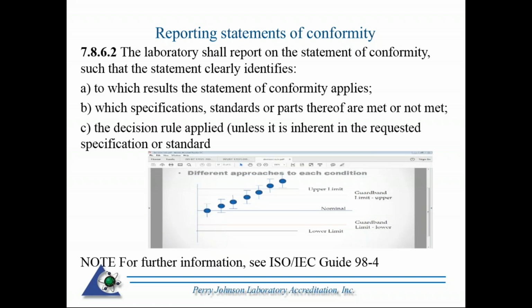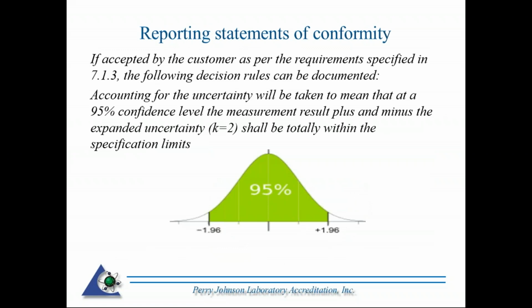7.8.6.2: the laboratory shall report on the statement of conformity such that the statement clearly identifies to which results the statement of conformity applies, which specification, standards or part thereof are met or not met, and again, the decision rule applied, unless it's inherent in the requested specification or standard. So that C there, that could be utilized a lot with some of the testing results. It could be specified within the procedure what the inherited decision rule was. And I have an example of that coming up here very shortly.